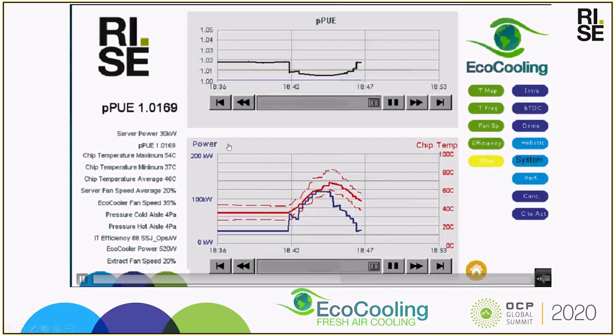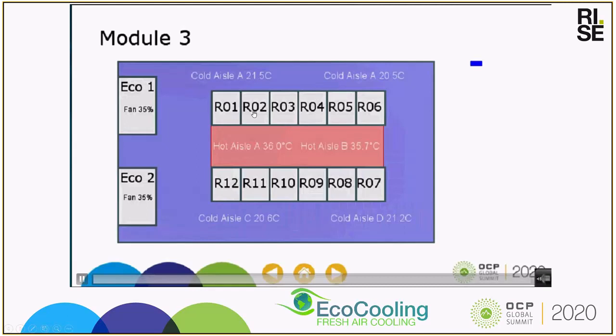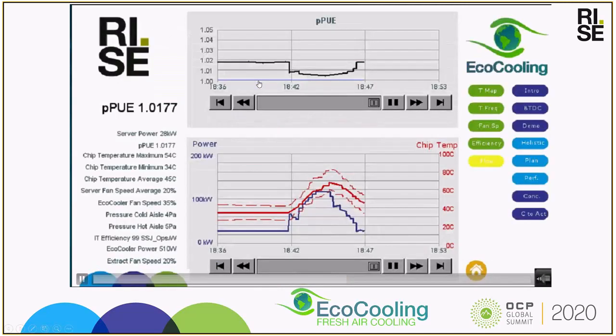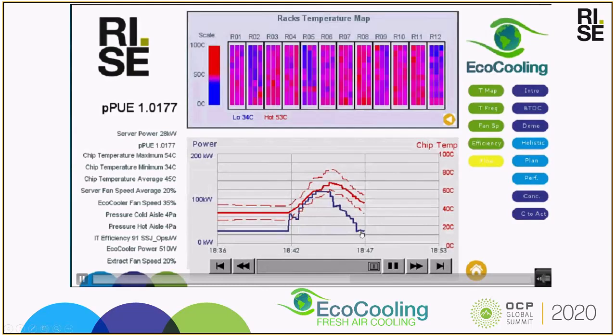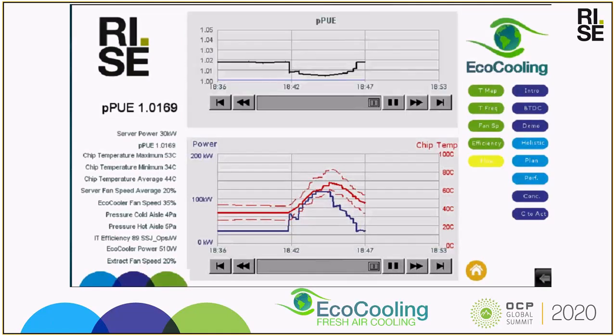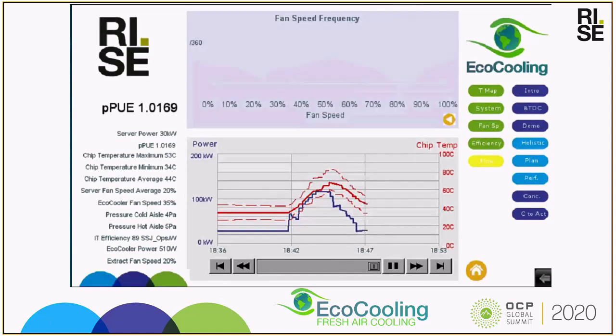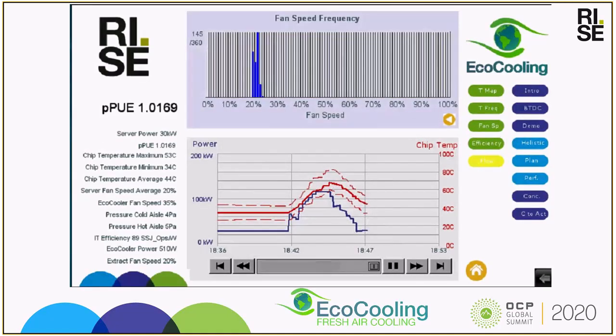supply fans. And the PUE you can see there, so the hot aisle temperature is now at 36 degrees centigrade. Cold aisle still maintaining 21 centigrade. So we remain at idle for about a minute, and then this workload was generated using stress-ng. Stress-ng can stress the CPU, so you can invoke a number of cores from the CPU. Now we're going to run using M prime. So M prime will stress all of the CPU and all of the memory.